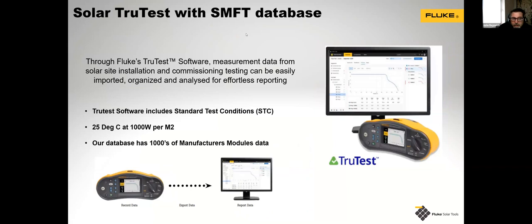So along with this, we have our software, which is actually interchangeable, bidirectional in terms of data. So we can record data and export it to the report itself, but we can also take the database from the manufacturers and give an ideal test situation that can be downloaded to the tester itself, and we can look at whether the panel itself is performing correctly as per the manufacturer's guidelines. There are thousands of manufacturers and they're always increasing, but because TruTest is updatable via the web, that information is constantly being updated on our TruTest software.